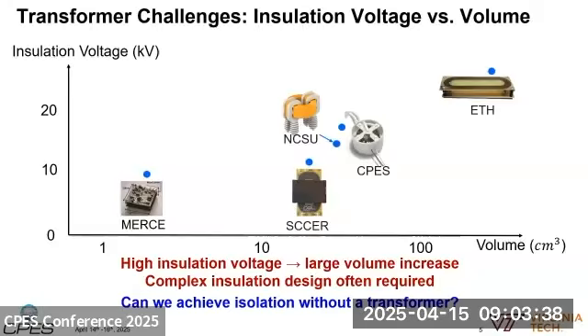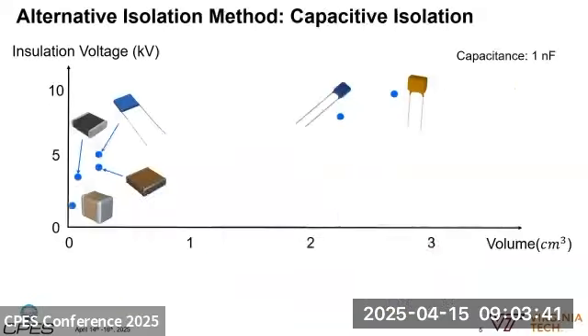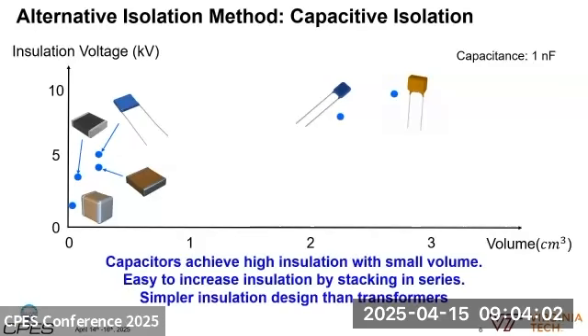So the question is, can we achieve isolation without transformers? As an alternative method, capacitor isolation serves the same function. For example, a 1 nanofarad ceramic capacitor can go up to 10 kV with very small volume, and because of the simple design, you can easily stack them in series to double the insulation voltage, which simplifies insulation design a lot compared to transformers.